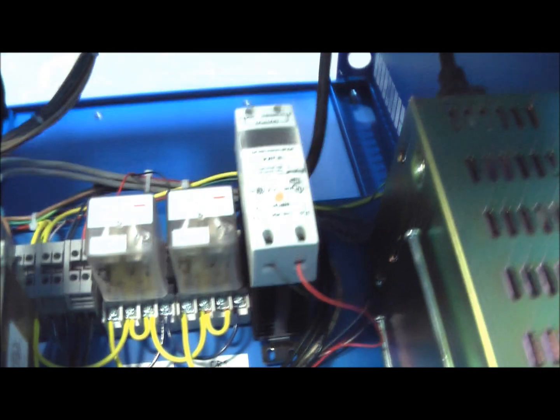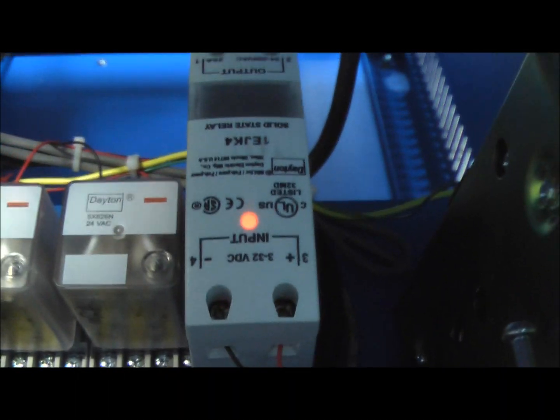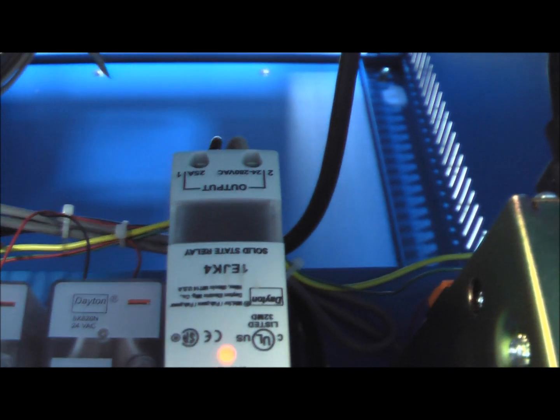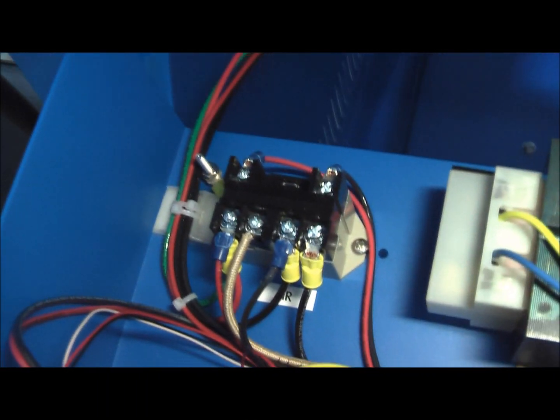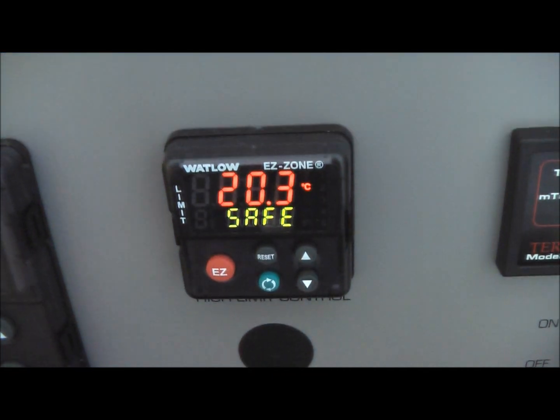We'll see that the red light came on. So when the red light's on, you should be able to put a voltmeter across the output and read the power. Now, just because the red light is on doesn't mean power will be coming out of here if the safety relay has tripped.